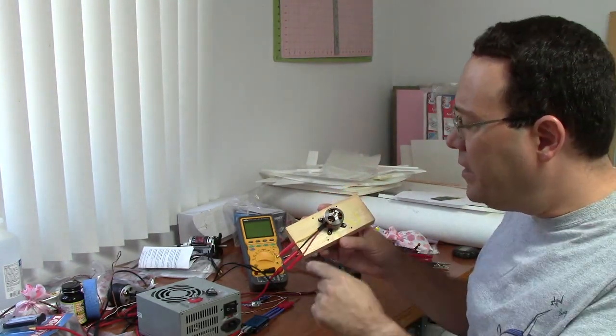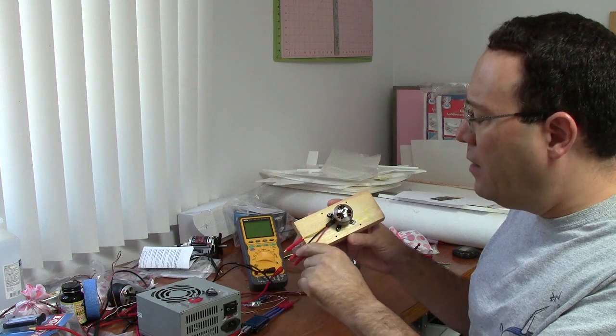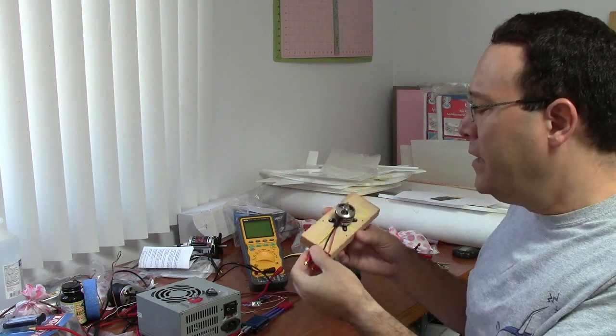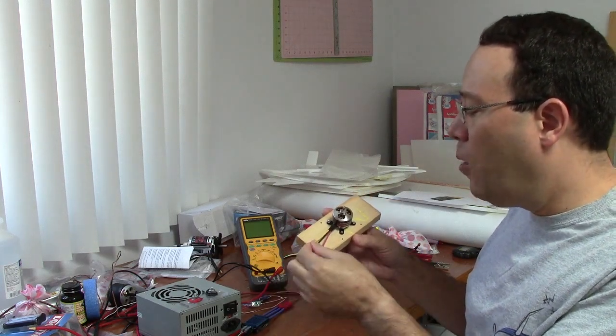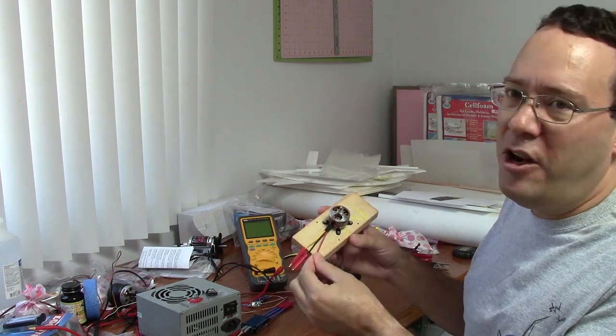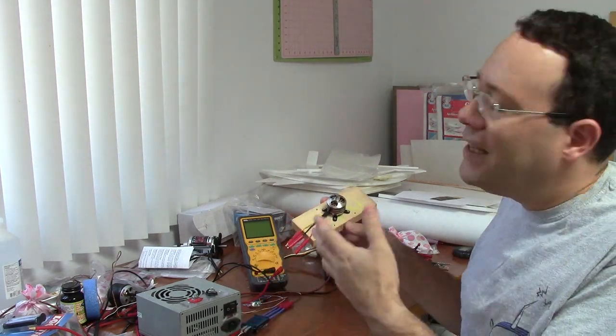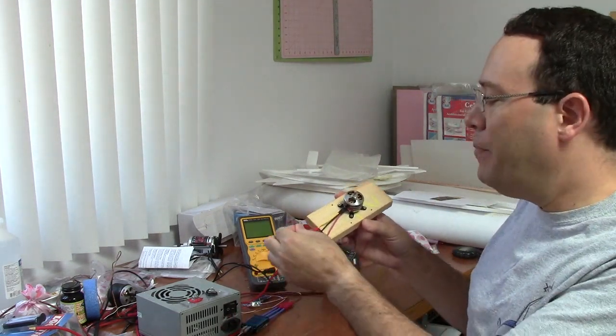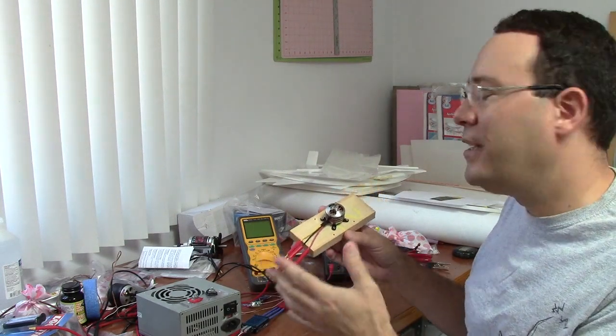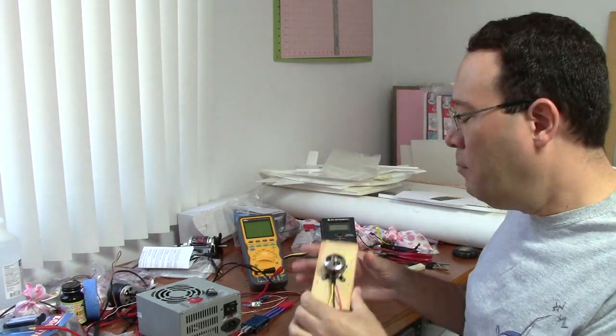Motors actually have three windings, three wire loops through them. So if you measure one and then measure another one, you'll get a little bit of a different value. If you're really paranoid about this, I will measure all three and then take the average. I'm not sure you have to do that. I know they'll all be pretty close anyway, but that's just one thing to watch out for. But otherwise, this is a really accurate way of measuring the internal resistance.